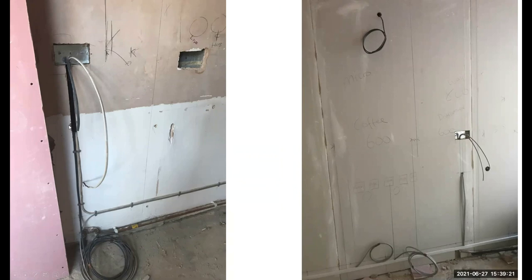And once the kitchen cupboards are in front, it's hidden in the void, nobody's going to see any of that. On this side, I've got a plasterboard wall, so it wasn't easy to clip the cable. So what I've done here is I've glued and screwed this conduit, this trunking to the wall, and I've used the trunking to hold the cables in place. And then all I'll do is come up to this kitchen unit behind here, which I'll show you on the next slide, and here to get to this socket. So there's always a way around it.